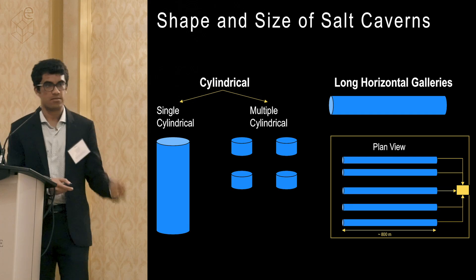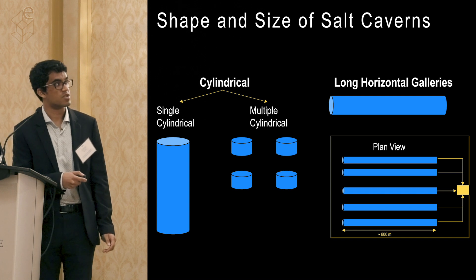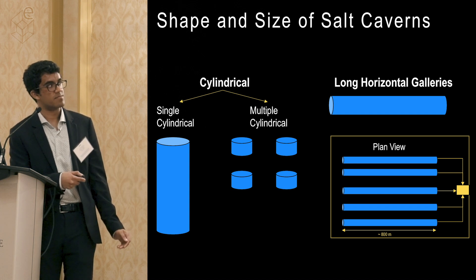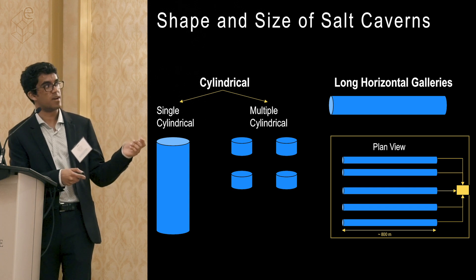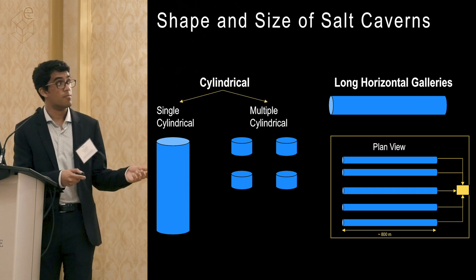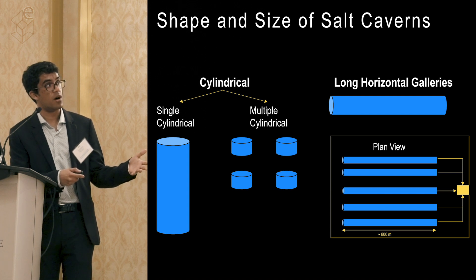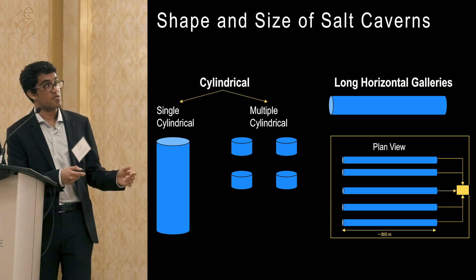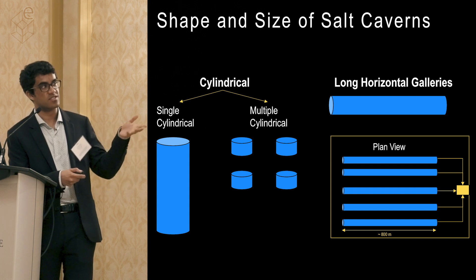We can then look at the shape and size of our caverns. We go with the traditional vertical long cavern, with length along the vertical axis — this is what's been used in Huntorf and McIntosh, Alabama. It's easiest to solution mine. If you don't have a thick enough salt deposit, you could use multiple cylindrical caverns — four of these to match the volume of one vertical cavern. If you have an even thinner deposit with high demand, you could do a long horizontal gallery — like a hot dog versus a hamburger. These are much harder to solution mine but viable depending on environmental constraints.